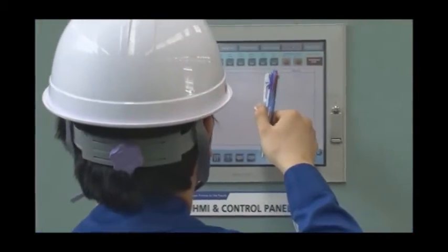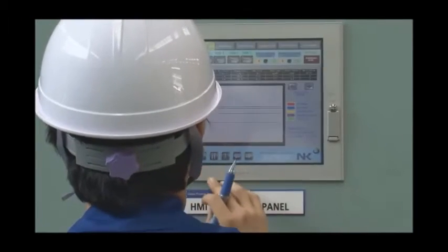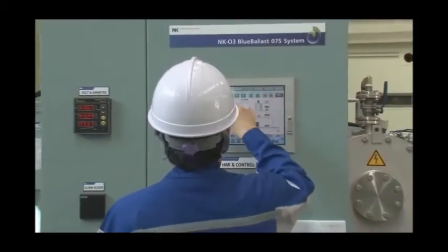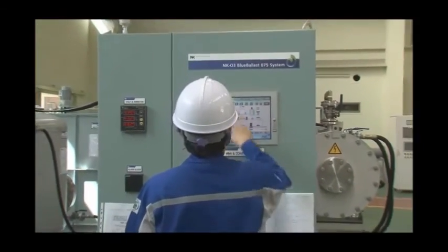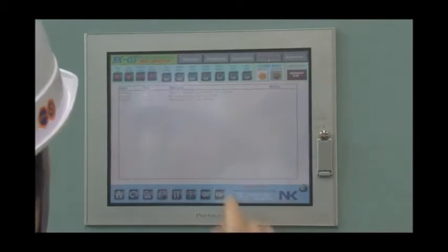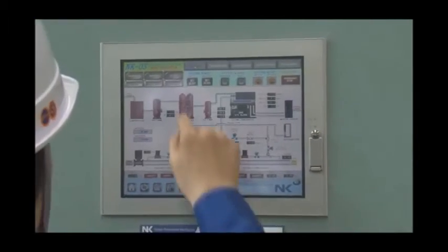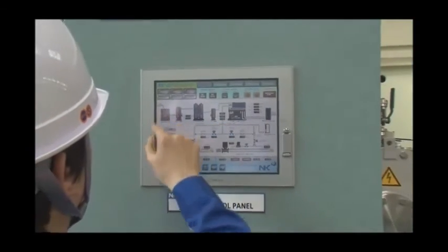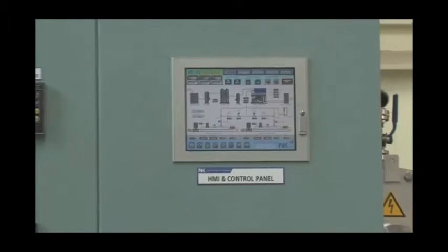All equipment and sensors are integrated and interfaced with this main control panel, which provides programmable logic controller and HMI, human machine interface. Full automatic or manual operation can be selectable according to the situation, but all operating status of NK-O3 BlueBallast system is automatically recorded in real time. Also NK-O3 BlueBallast system is interlocked to ship ballast management system and in emergency case, interlock can be overridden manually.